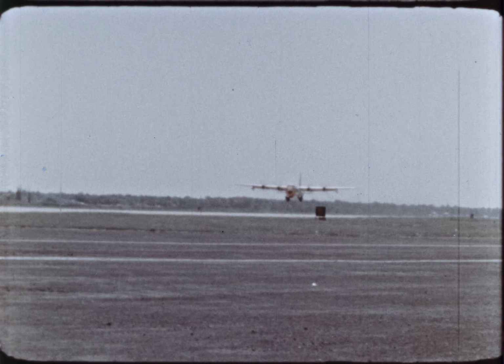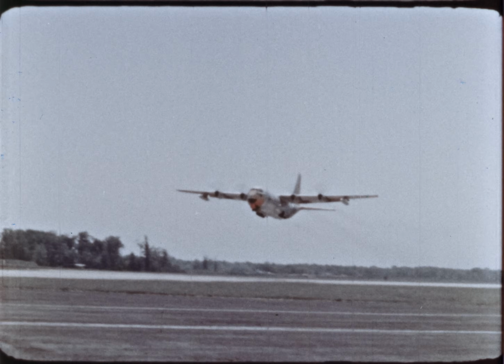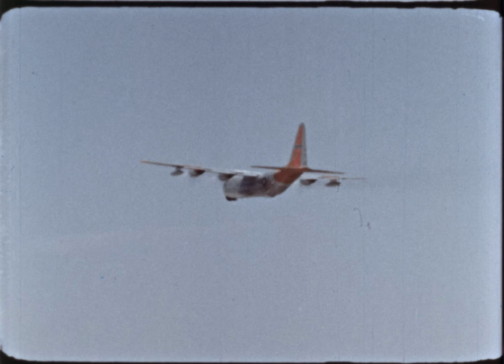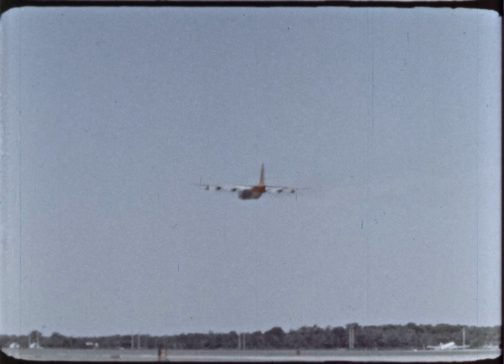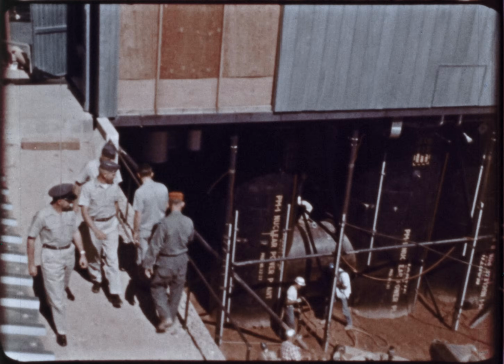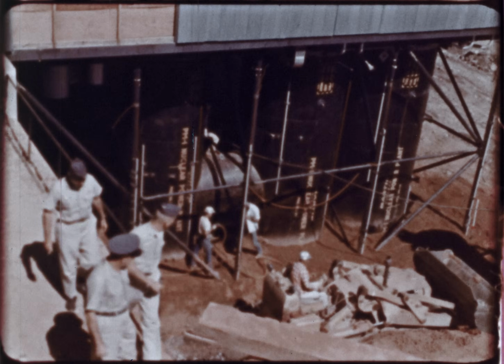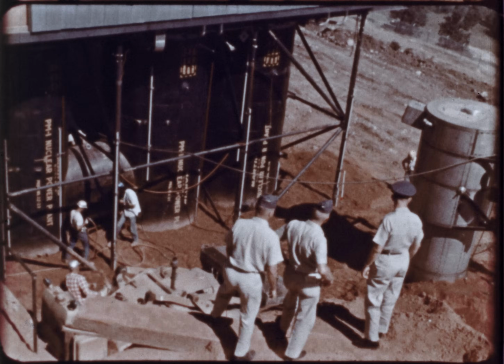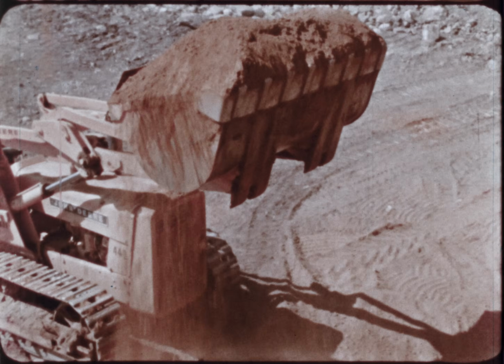Beginning May 29, 1961, C-130 aircraft flew PM-1 packages to Ellsworth Air Force Base, South Dakota, for the overland trip to Warren Peak. The PM-1 was reassembled at the site on previously prepared foundations. The 4 tanks of the primary system were erected on foundations 30 feet below floor level. Backfill of crushed rock is packed around the tanks as a shield to reduce radiation to a safe level.